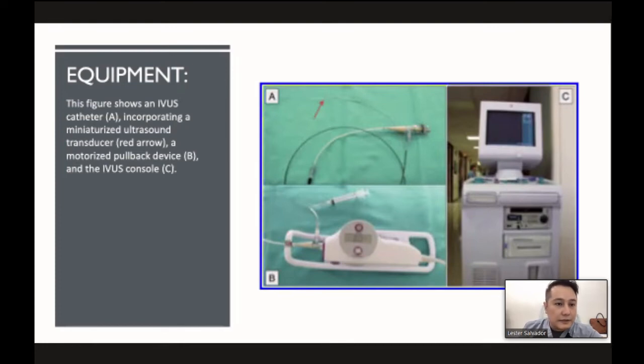The next one, in figure B, is called a pullback device. The transducer pullback can be performed either manually or using a motorized pullback device such as this one. It withdraws the catheter at a constant speed of around 0.25 to 1 millimeter per second, but most frequently at 0.5 millimeter per second.